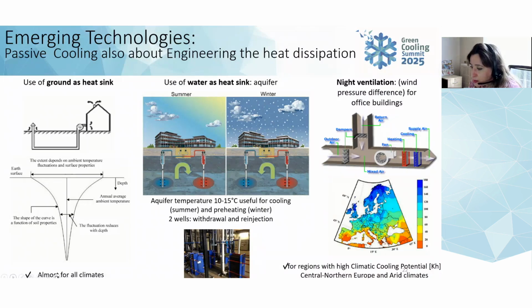The middle figure I'm speaking about here, water, can also be used as a heat sink, in particular in areas where aquifers are available, whose temperature is often in the range of 10 to 15 degrees Celsius, which is also useful for cooling during summertime and preheating during wintertime. So I'm showing here the summer and winter figure. This consists of drilling 2 wells, one for the warm water withdrawal, and the other one for the reinjection to the underground heat exchanger.